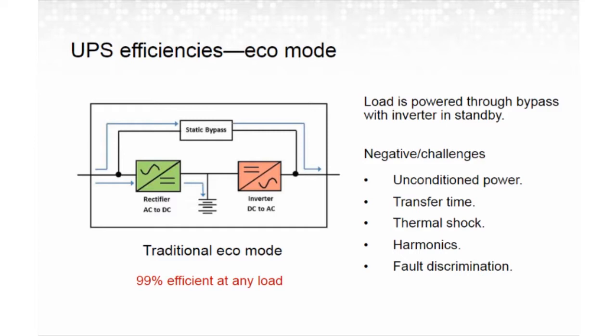The other is transfer time. Basically, during an outage, it takes time for the UPS system to detect the failure, turn on the inverter, transfer to the battery, and then open the bypass switch. Although it is fast enough so that the load doesn't see it, there are other components that can be affected, such as a transformer could saturate, and then when it gets restarted, it will have a large inrush of current that could trip breakers. Your static transfer switches downstream could see it as an outage and try to change state. So there are other things involved with the transfer time.